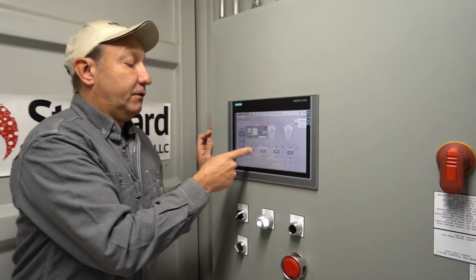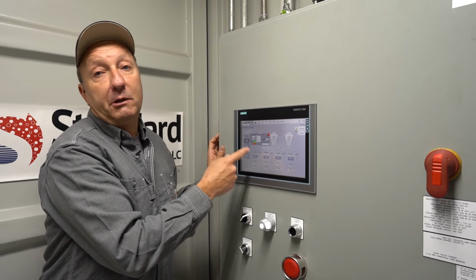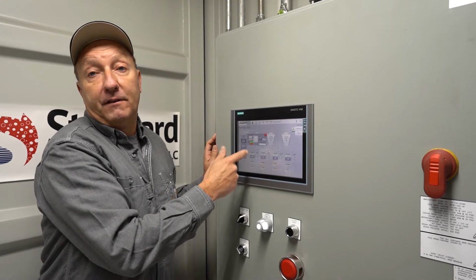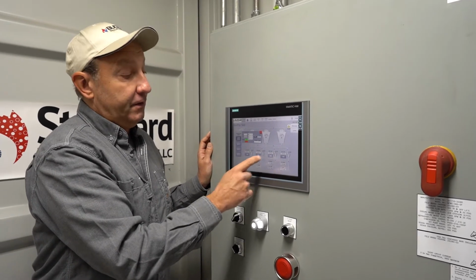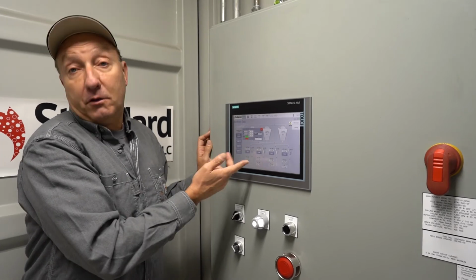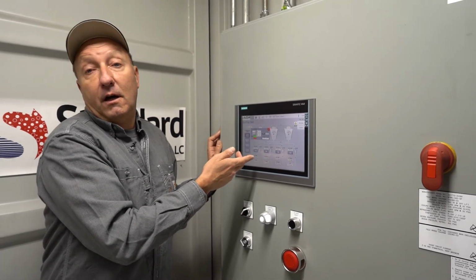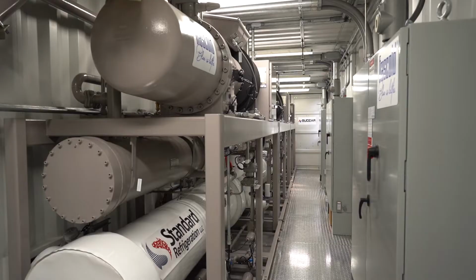and I can do the same thing to tune the variable frequency drives, VFDs, for the tower pump systems. Each one has its own tuning block. This also can be used for manual function or troubleshooting purposes.